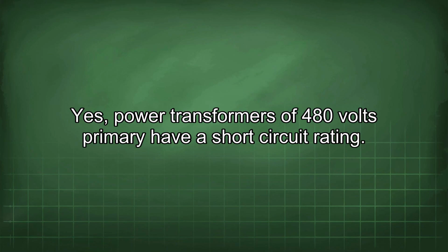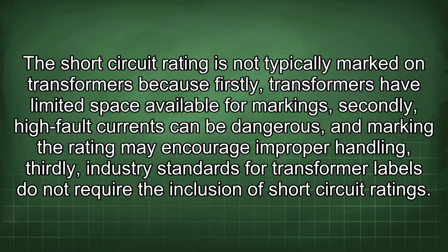Yes, power transformers of 480 volts primary have a short circuit rating. The short circuit rating is not typically marked on transformers because, firstly, transformers have limited space available for markings. Secondly, high fault currents can be dangerous, and marking the rating may encourage improper handling. Thirdly, industry standards for transformer labels do not require the inclusion of short circuit ratings.